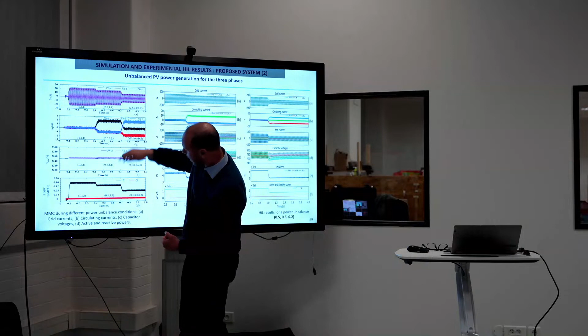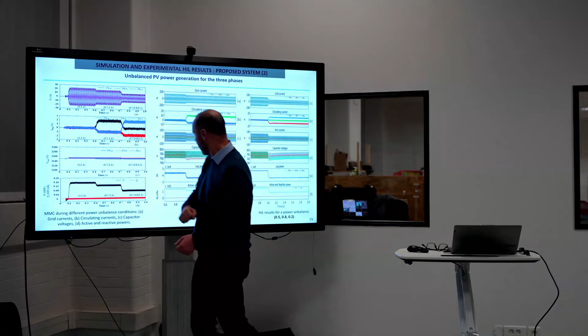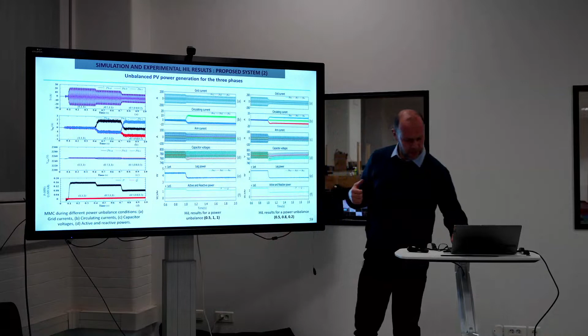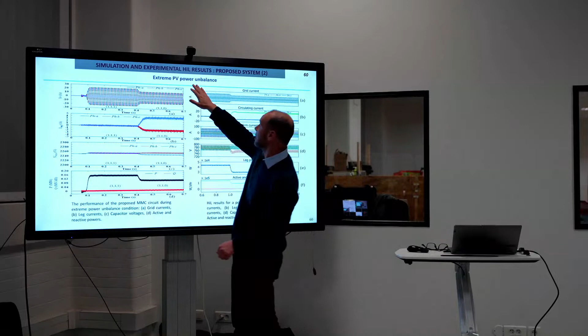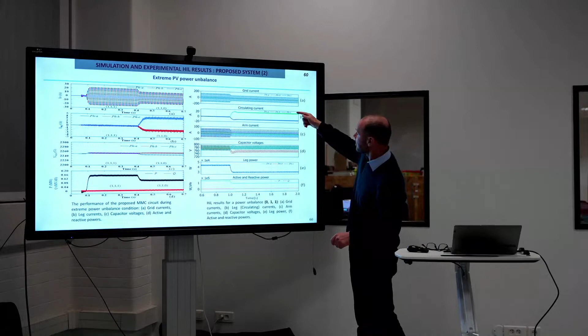And then we changed the power, and you can see it. We tested a 200 kilowatt system. When the power is changing, it follows exactly without any fluctuations. And these are the capacitor voltages. We also did the test at extreme power levels. Extreme power imbalance means one is 0, another one is full. You can see exactly they will balance each other. You can see the power dropping from the maximum to half. And also the circulating currents cancel each other.